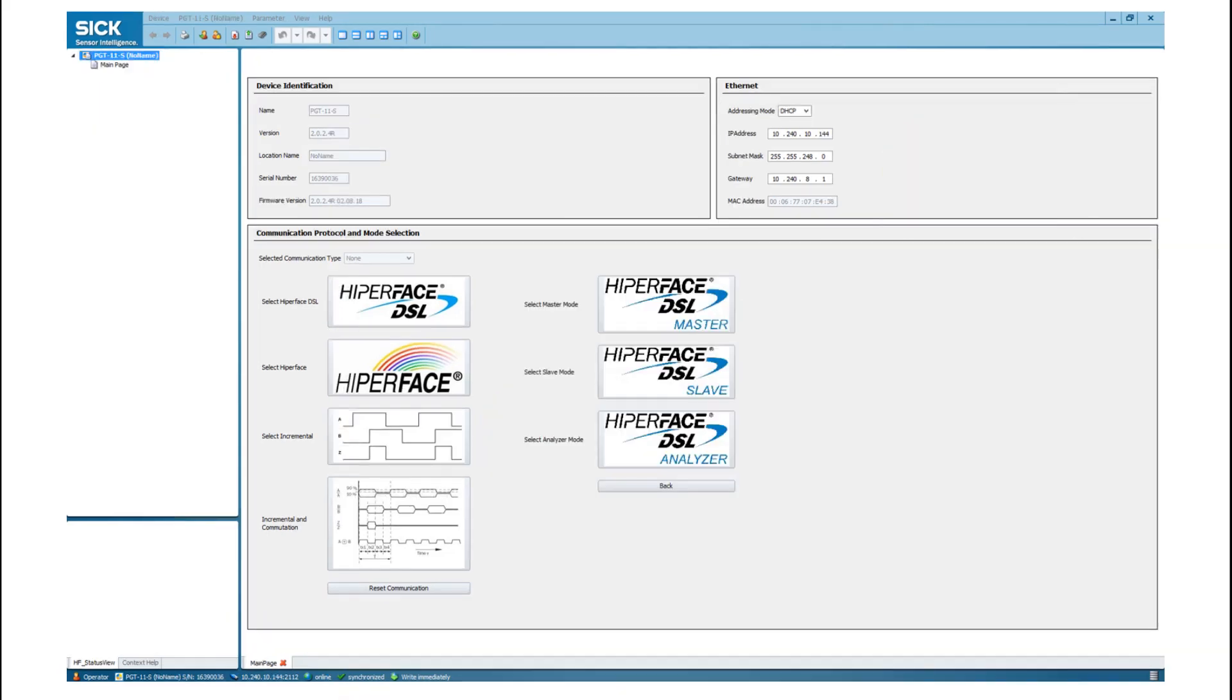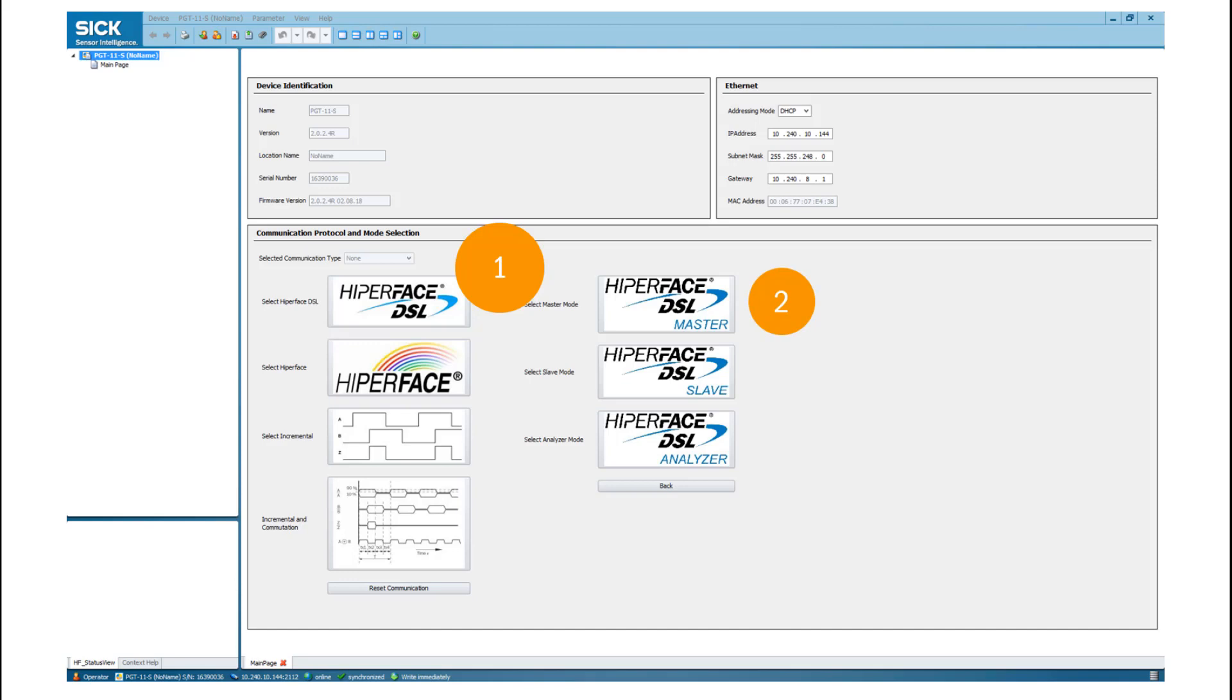This tutorial deals with the Hyperface DSL mode. Therefore, please click on the Hyperface DSL icon. Now three mode selections appear. The master mode offers functions like set position, preset position and data field management. In the slave mode, the PGT11 simulates a motor feedback system. Core functions of the analyzer mode is to check the communication on the line. Please choose the operation mode accordingly.